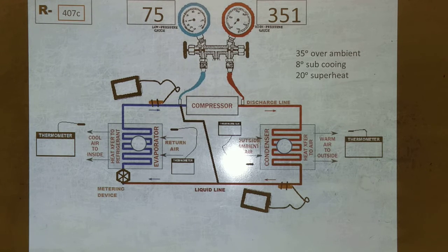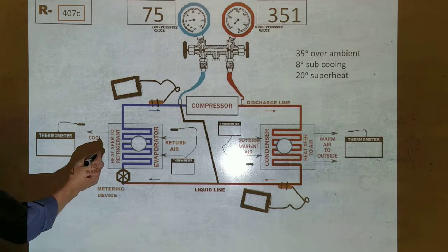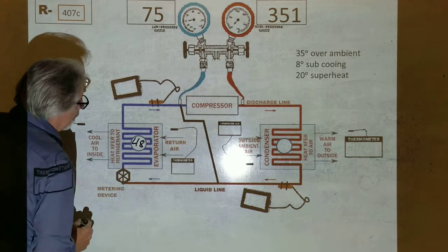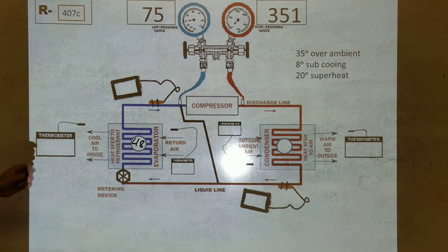Okay. So we know what our temperature should be at the saturation point, right? Because you just went up there and put your gauges on, and you got pressures. What do they mean? So it's gonna be 48. 48 or 44? 48 degrees on that coil. And the high side is what? The high side is 132. Okay, so we're condensing at 132 degrees.